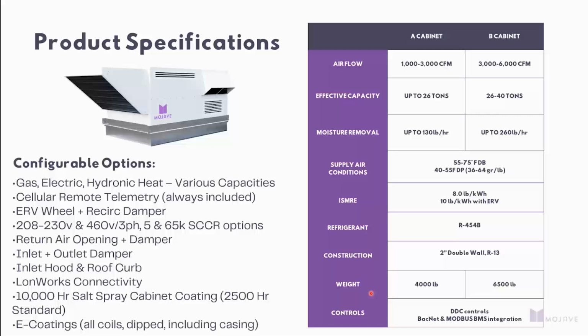Controls wise, it is factory packaged controls and pre-programmed as well. That said, we could work on custom sequencing if required, but it is factory packaged controls, with BACnet MSTP, IP, and Modbus all standard. Additionally, we are providing a cell modem on every product, made available at no additional cost to the end user, capable of remote monitoring, diagnostics, and trending. Beyond that, we do offer a built-to-spec style a la carte menu of options, some of which are listed on the screen here. And we have a bunch of additional options not listed here, but a la carte, built-to-order style product.